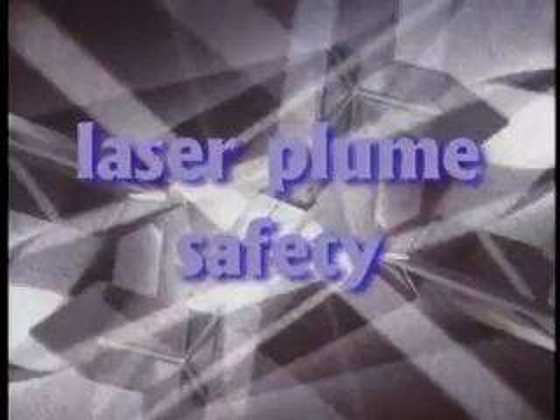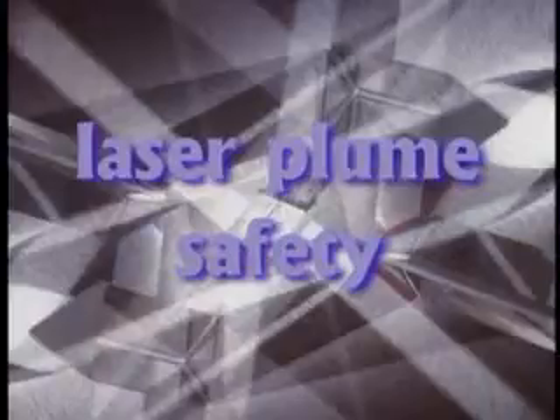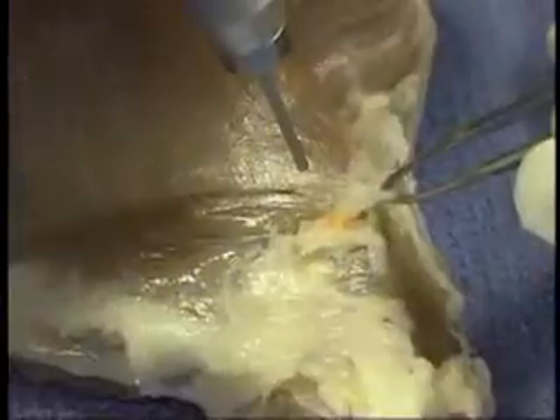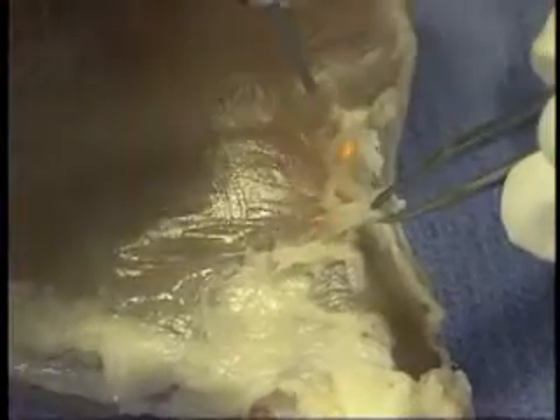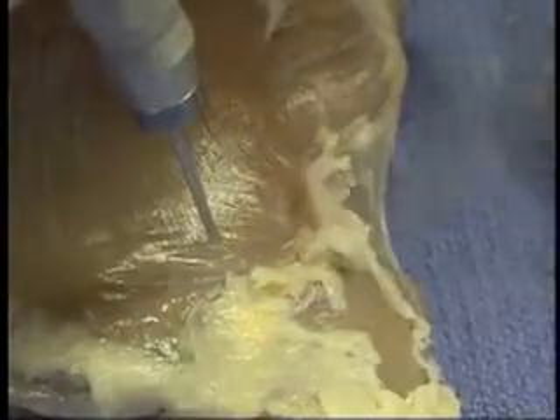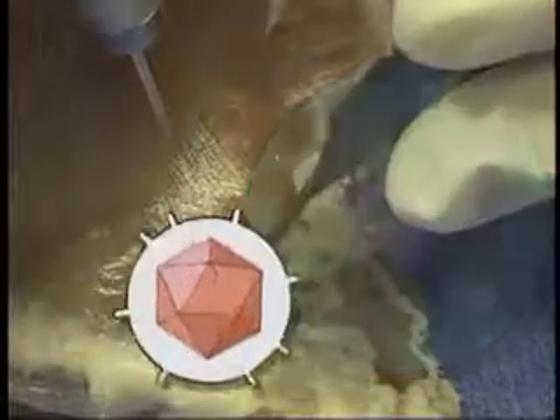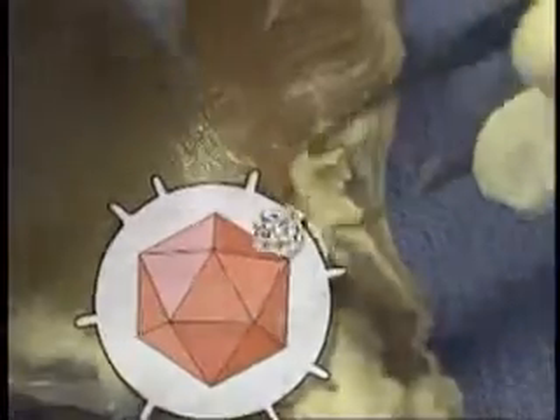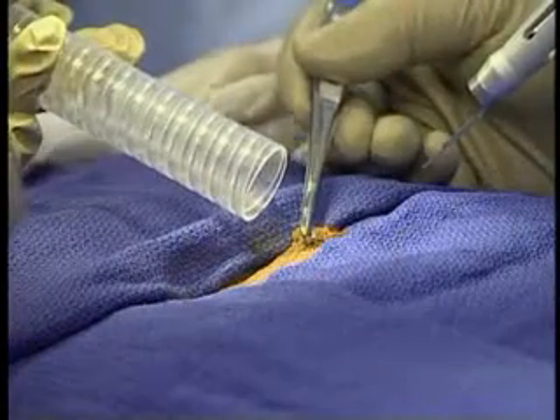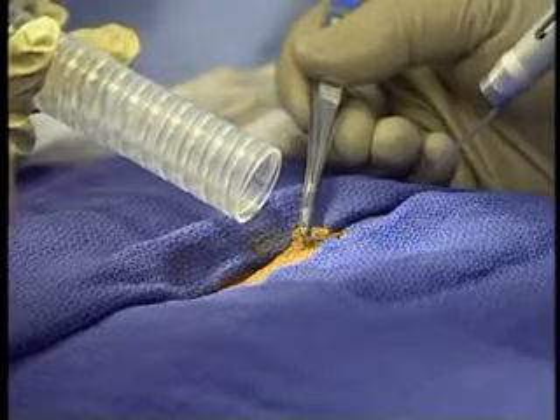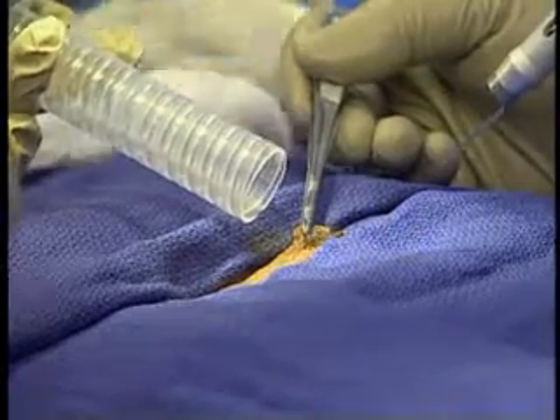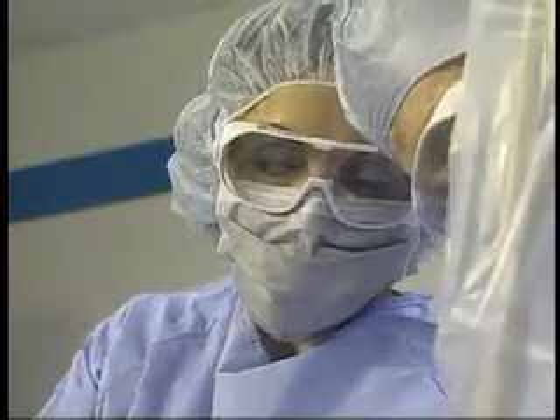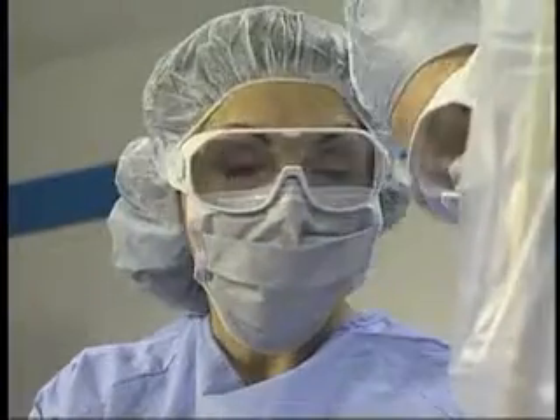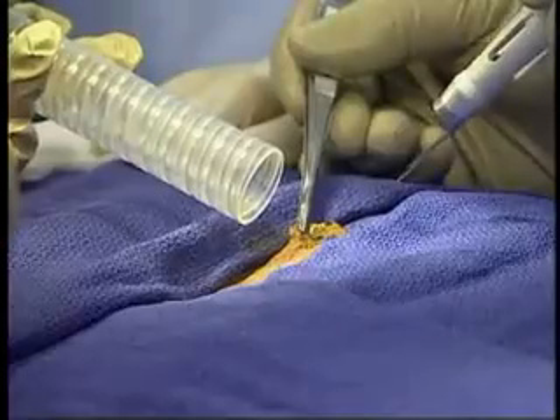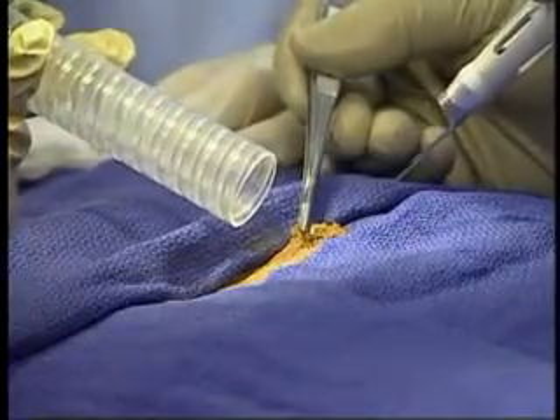To use the smoke evacuation wand effectively, place it as close as possible to the site of plume origin. High filtration masks help filter particulate matter and may reduce noxious odors. These masks should not be viewed as absolute protection from laser plume components and must be used according to the manufacturer's instructions. Smoke evacuation systems are used by healthcare providers as the first line of protection against occupational exposure to laser-generated airborne contaminants. A smoke evacuator is a vacuum pump with a filtering system.